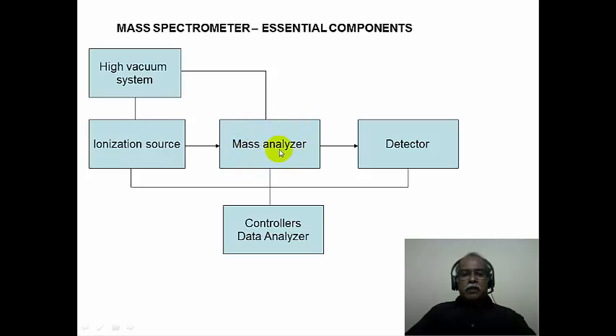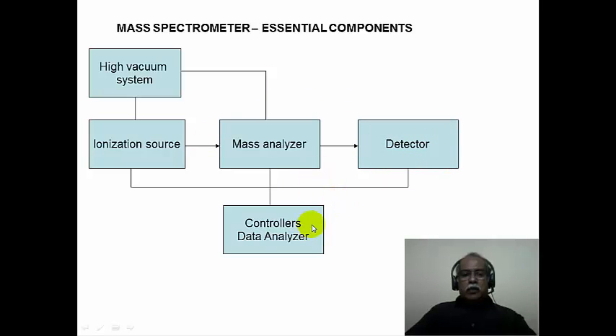There are several different types of mass analyzers available. The mass analyzer essentially separates ions of different masses and segregates them based on their mass-to-charge ratio. The ions thus separated are fed into the detector, which detects them and puts out a signal recorded as a mass spectrum. The whole system is controlled by computers and microprocessors, which form the data analyzer part of the mass spectrometer.